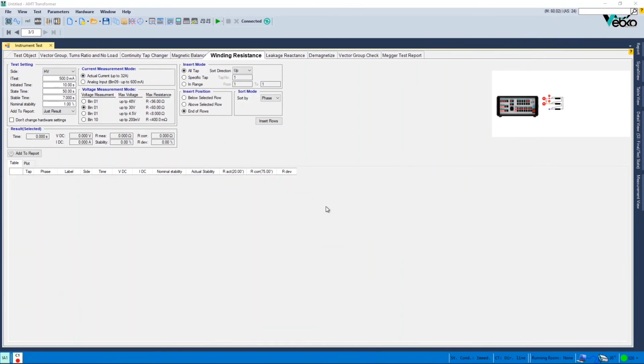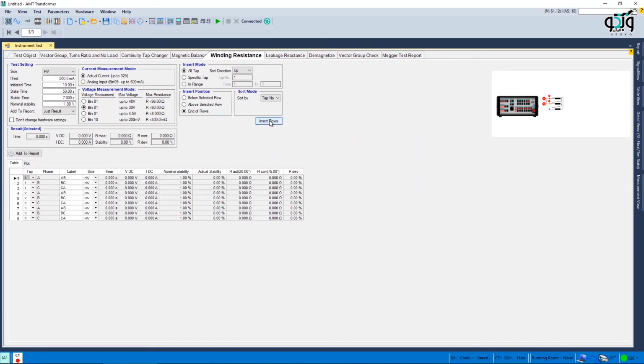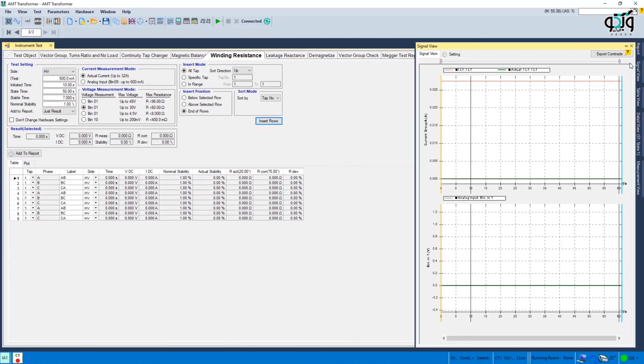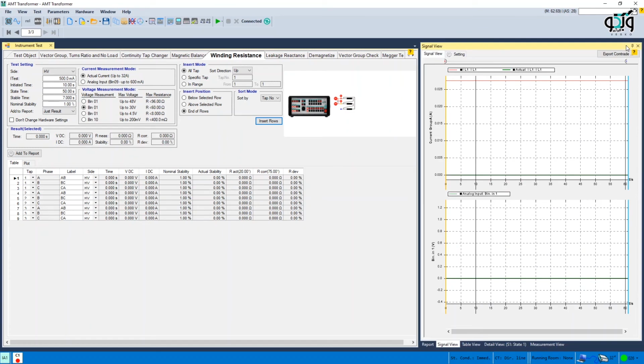Running the test and analyzing the results. To perform this test, for example, the HV side with 3 off-load taps and 0.5 amperes of current is tested for all 3 taps. The setting related to time is left at its default, and Sort By is set at phase, and then by pressing Insert Rows, the test table is created. The signal view window is open so that it's possible to view the current changes and the voltage. To perform the test, the first row is selected.